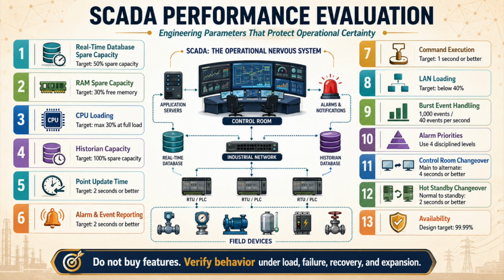The 12th engineering parameter is control command execution time, because a command must never feel like a suggestion sent into a void. When operators issue open, close, start, stop, reset, enable, inhibit, setpoint, or mode change commands, the system must transmit the command, receive confirmation, show intermediate states, handle timeouts, and represent success or failure clearly. A 1-second command execution target is aggressive but meaningful where field devices and communication paths support it.